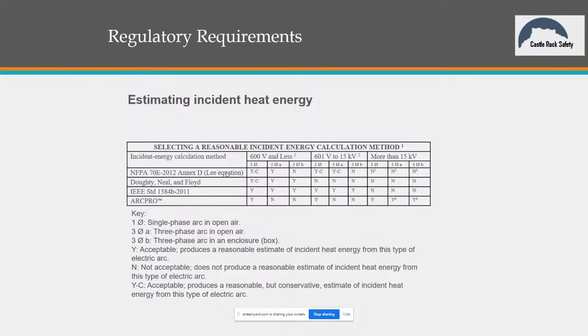There are only 2 that have, and that's IEEE 1584, of course. And that one is limited again to 3-phase only and 208 up to 15 kV. The only other option we have is ArcPro. ArcPro is a software package from a company up in Canada that you can purchase, and these are equations that have been verified in a lab. This is empirical, not theoretical. And so OSHA recognizes ArcPro as the best system for calculating incident energy on the utility side.